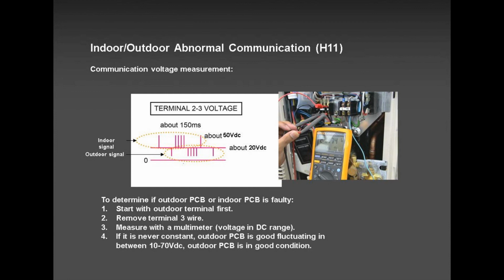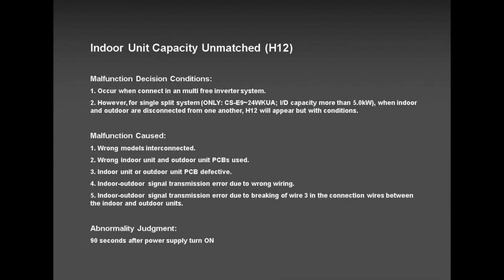So what is H11? H11 is communication error between indoor and outdoor. And I'll tell you, after working with all other companies, it was so hard to determine whether the problem was inside or outside. But with Panasonic, it's super easy. How you do it? All you do is you remove the terminal 3. You see here, it says remove, disconnect terminal 3 wire on the control side and measure between 2 and 3. And when you get a fluctuating voltage of up and down between 10 to 50, 10 to 70, 10 to 50, all the way up and down, your outdoor board is good. Your indoor board is a problem.